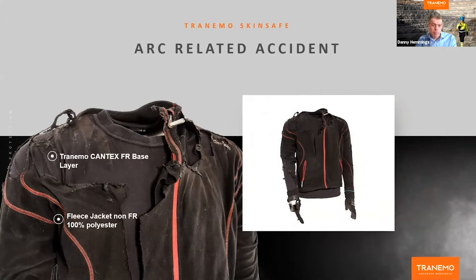Again, this is a good example of that. So you have there, and this is garments that came from an actual incident in Scandinavia, one of our base layers, which is a sweatshirt base layer, flame retardant arc garment, and the wearer put a 100% polyester fleece jacket over the top. So clearly not an FR rated or arc rated product. You can see from the drop shot there, right side leaning in, and effectively it's destroyed all the fabric on the polyester fleece up the arm.